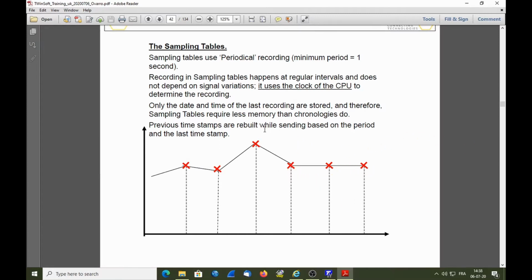The principle of recording is also FIFO, first in, first out, and here also you define a size which corresponds to a certain period of time of recording. The value that you record can be a minimum, a maximum, an average, an instantaneous or an incremental based on the period. We will see that in detail when we do the configuration.